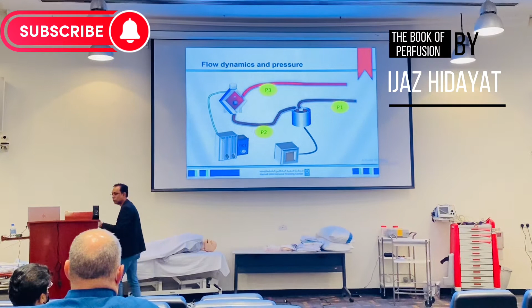Why are we focused on access pressure? Because when we are sucking blood from the body with the kinetic force, with the magnet, with the coupling of the motor, and we are sucking with a higher RPM, there is a chance of shear rate and shear stress increase, and it can lead to the destruction of the cells, and you will find hemolysis mostly. So you have to maintain the flow and the pressures within the normal range. So access pressure is very important. Sometimes your patient is hypovolemic and you are sucking more, which can lead to cavitation, and you can make an embolism. The air lock will come up, and you will not get a good chance to return the flow back to the patient. So the access pressure, your P1 pressure, is very important.